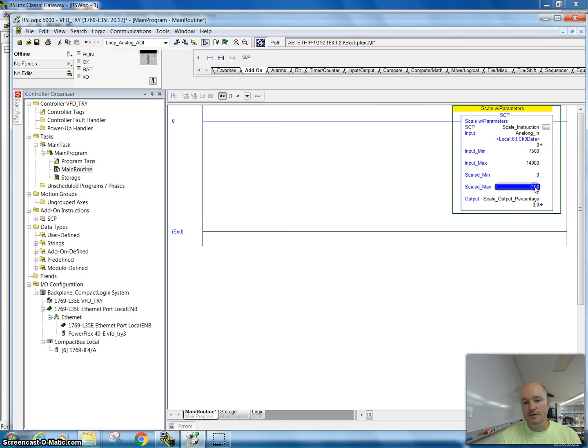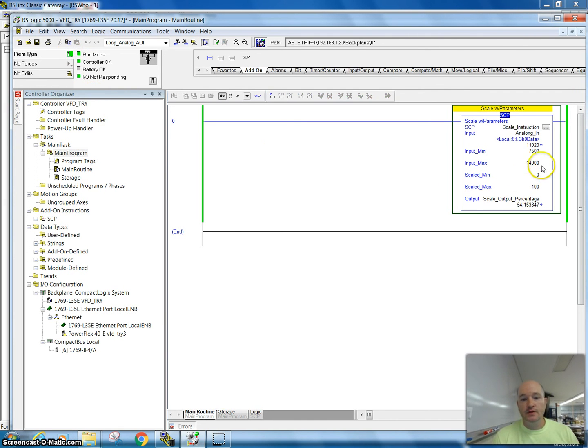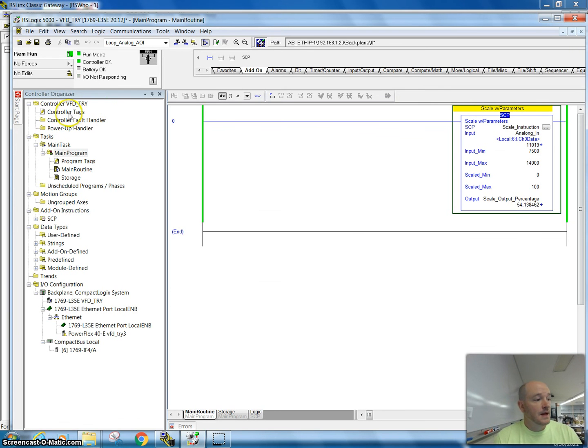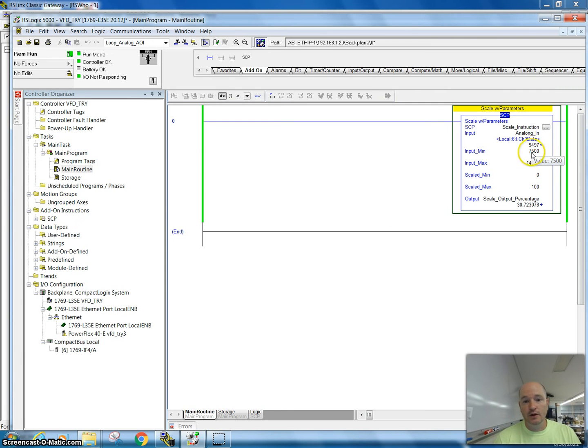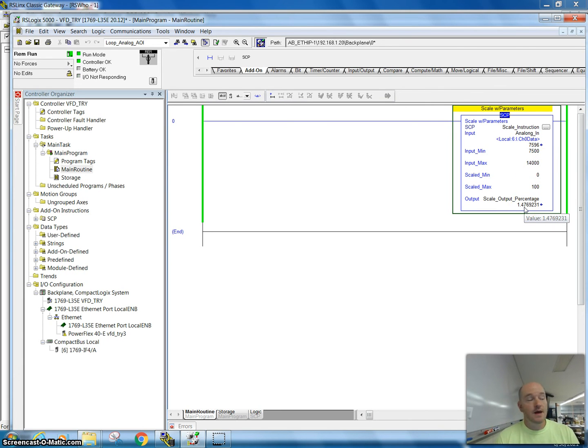I just put these values in here, and if I were to download this it would 100% work. So we'll go ahead and download this. You'll notice that my analog input is at about 11,000, and that puts us at about 54% full. Now the analog signal is coming from analog channel 0 on slot 6. As I adjust the signal lower, we're getting closer and closer to 0 — there's a little residual liquid in the tank, so we're at around 1.5%.